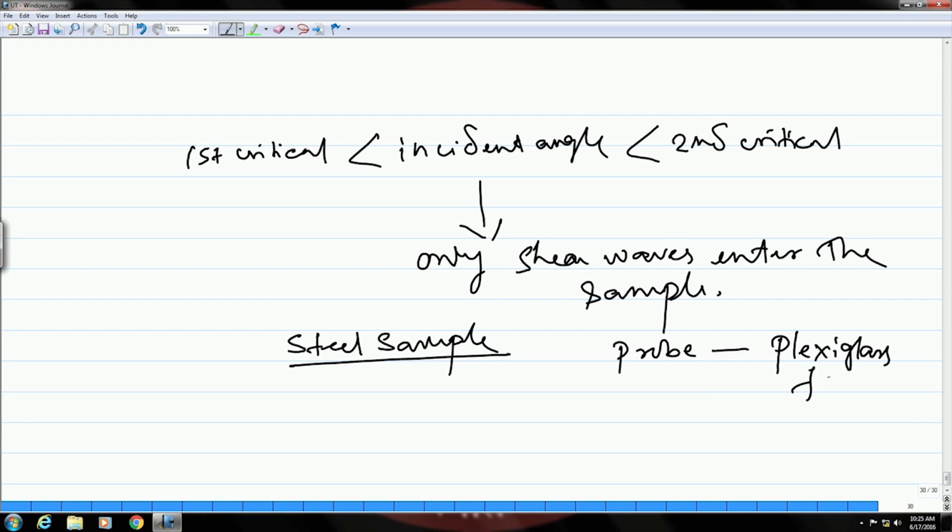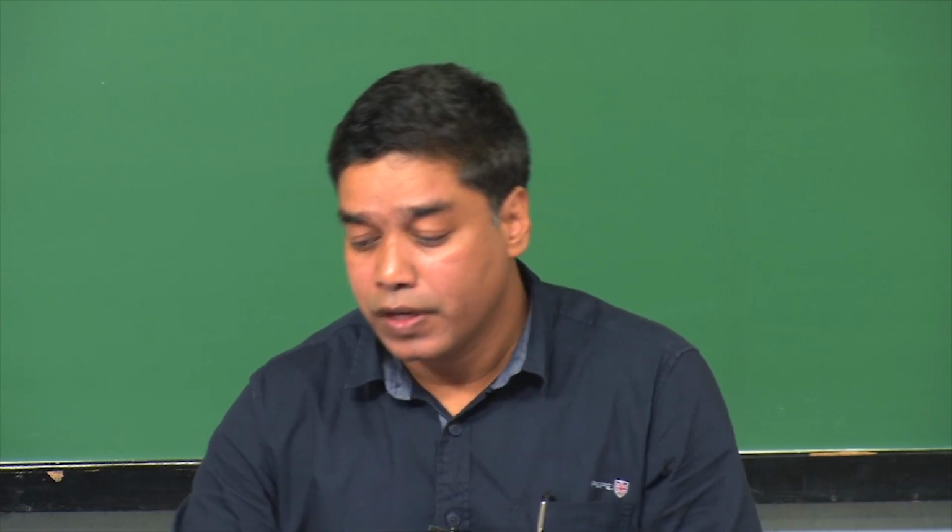Okay. So, the front face just in front of the active element, if you have seen the construction of ultrasonic probes, is some kind of fiberglass kind of thing is there, just to protect it and also keep it inside that housing.